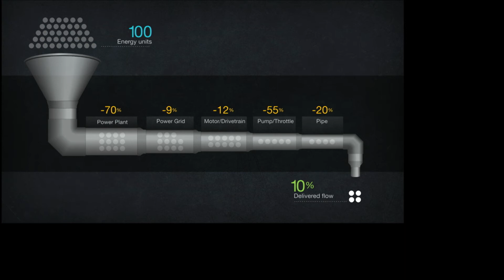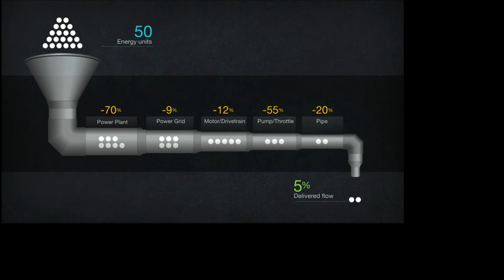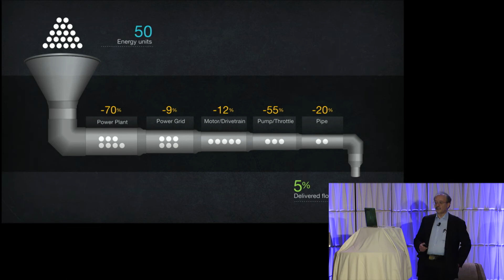But now turn those compounding losses around backwards from right to left into compounding savings, and every unit of flow or friction you save in the pipe saves 10 units of fuel cost, emissions, and global weirding back at the power plant. And as you go back upstream, the components get smaller and cheaper, so the total capital cost goes down. Now let's apply this logic to big data centers.